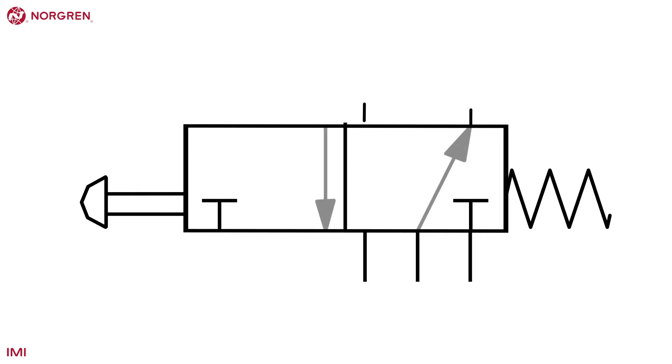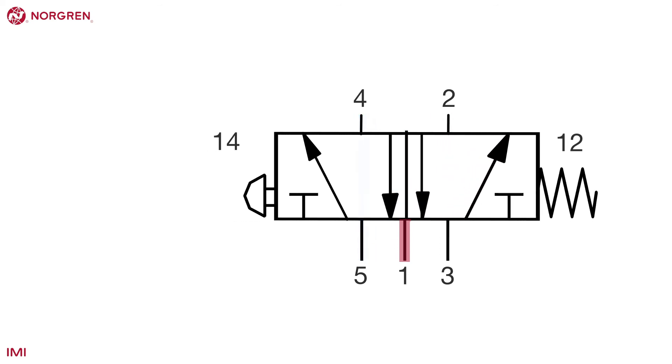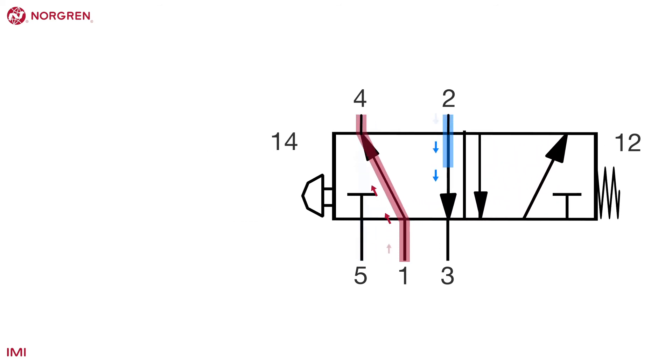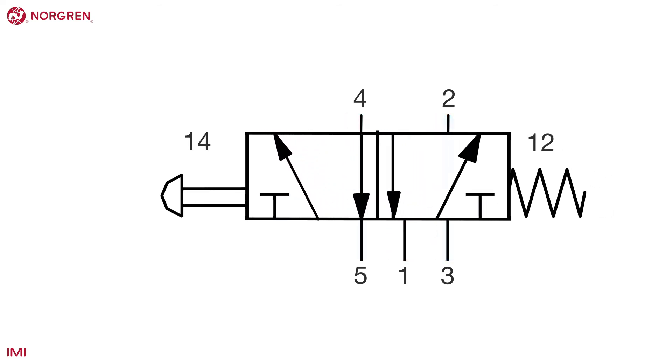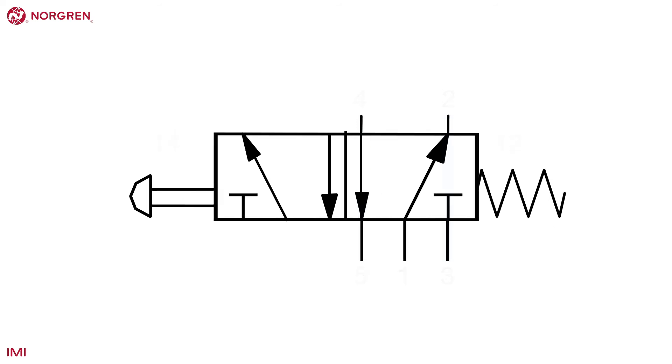You can see the operation more clearly in this diagram. Two boxes represent 2 positions and the ports are numbered. When the air flows to port 2, the air from port 4 passes to the exhaust. When the air flows to port 4, the air from port 2 passes back through the exhaust. A 4-2 valve is less common and is not shown here. These valves are similar to a 5-2 valve, but share an exhaust port.